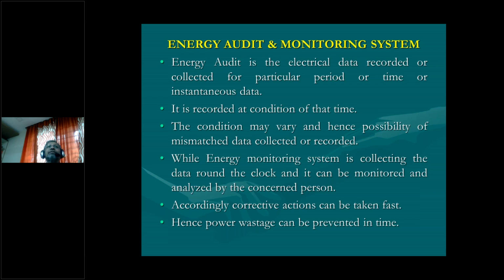So the better option is you should have some monitoring system in your industry, that is in your electrical system. So now the advanced generation of multifunction meters. Now we don't say energy meters, we say multifunction meters, where you will get all this cumulative as well as instantaneous parameter with connectivity. It may be with Modbus, Profibus or any connectivity, RS485, whatever it may be. And good softwares are available. You can integrate any number of meters. And with the help of software, you can monitor your energy.